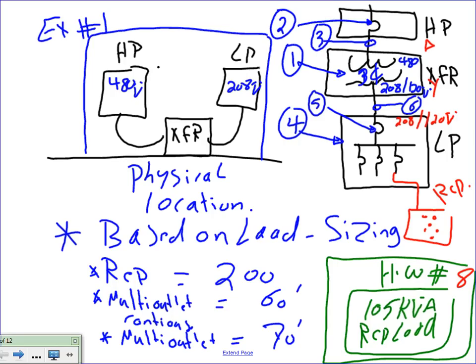When we size anything, Chris, remember the load calculation that you guys did with me? When we did the load calculation, you came up with kVA for the transformer, kVA for the receptacle panel, right? That's exactly what we're trying to do. I'm trying to find the kVA for the receptacle panel. Cool? Any question about the given before I move anywhere else? This is what you have.